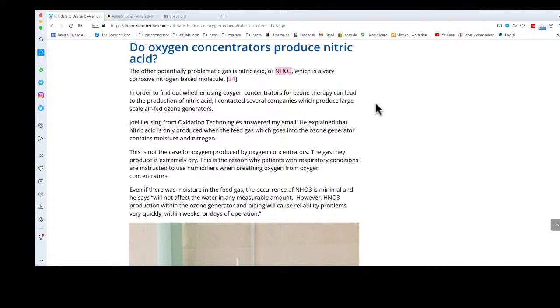Why? Because the gas is pressed through multiple filters, and all those filters extract moisture out of the gas. So the gas that comes out of an oxygen concentrator is extremely dry. It is actually so dry that most oxygen concentrators come by default with a humidifier, so that people who rely on oxygen concentrators because they have some lung problems first run the gas through water before they breathe it in, to moisten it. So he said that no, this is not possible. This is not something that happens when you feed oxygen that comes out of an oxygen concentrator into an ozone generator.